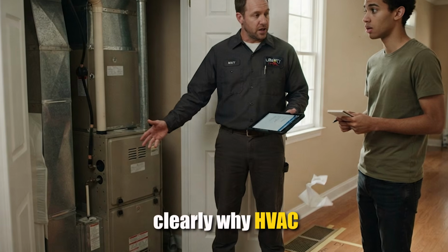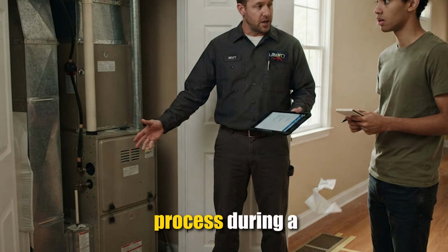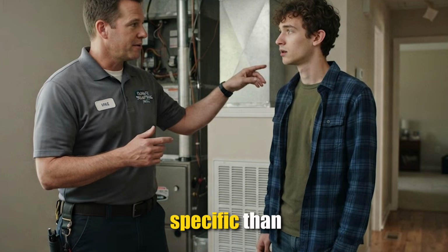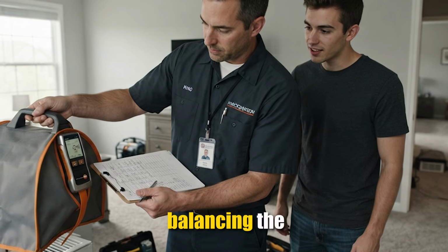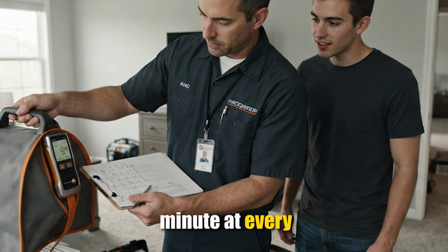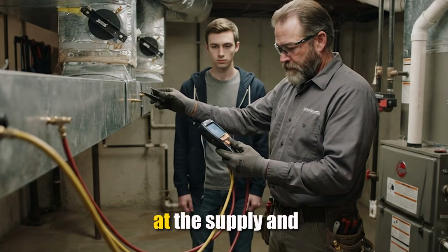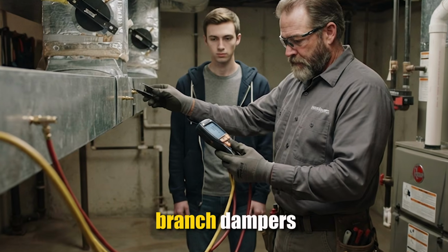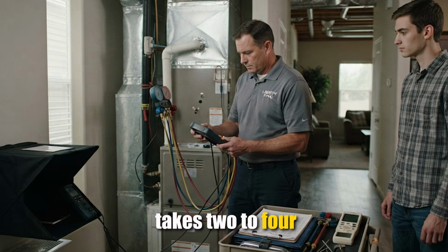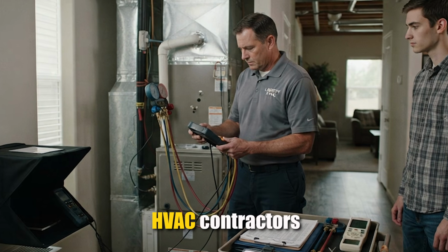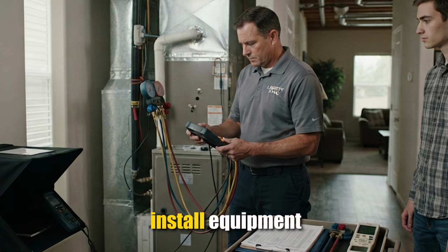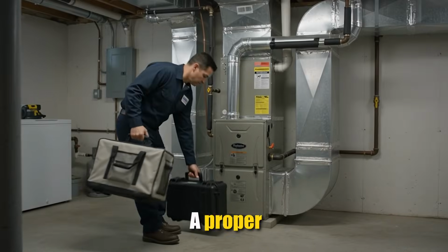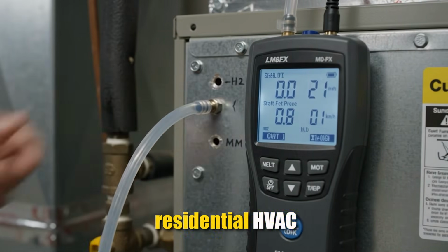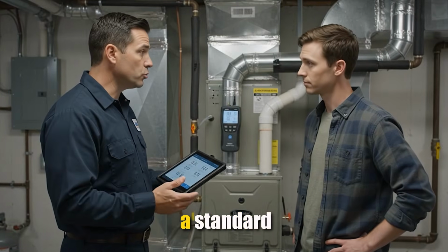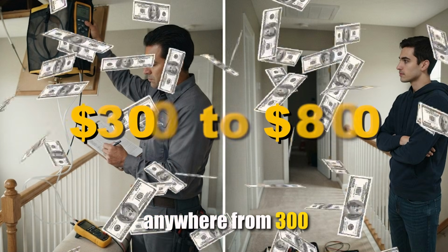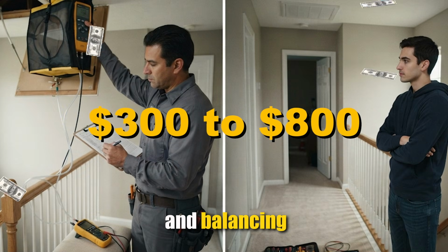Now I want to tell you clearly why HVAC technicians do not walk you through this process during a service call, because the answer is more specific than most people realize. Professional air balancing, the kind that measures actual cubic feet per minute at every register using a flow hood, checks static pressure at the supply and return plenums with a manometer, and adjusts branch dampers systematically, takes 2 to 4 hours and requires specialized equipment. Most HVAC contractors never measure airflow. They install equipment and hope it works. A proper professional air balance is a specialized service that most residential HVAC companies do not even offer as a standard option. The ones that do charge anywhere from $300 to $800 for the full diagnostic and balancing service.